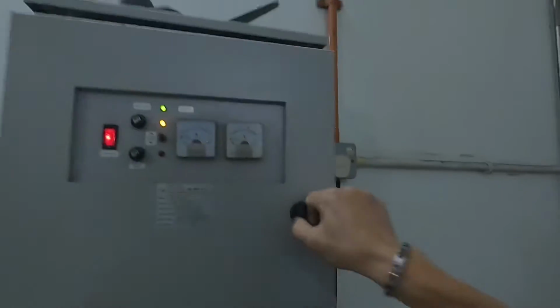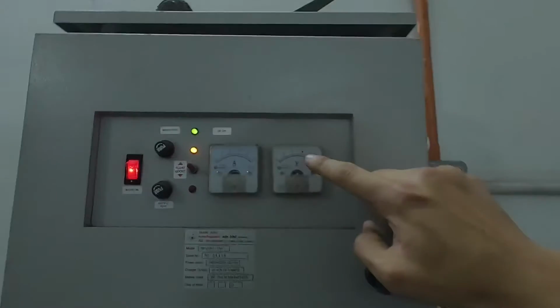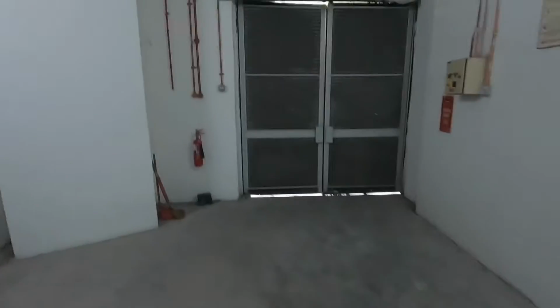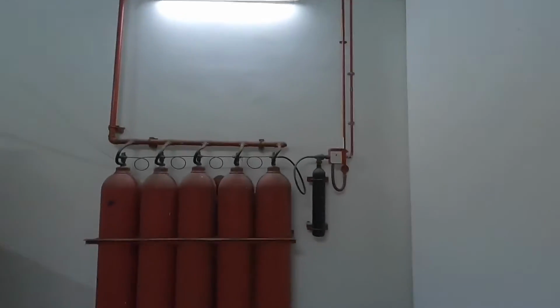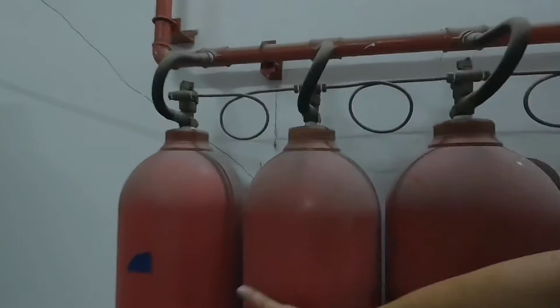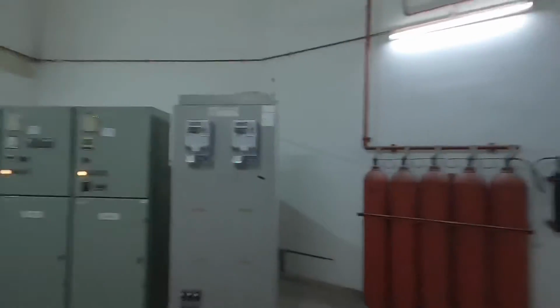Alright, then we have to make sure the safety parameters such as the tripping unit, battery is in good condition, voltage above 30 volt DC, charger function, rubber mat in place, fire extinguisher in place, CPR chart, electrical single line drawing, CO2 extinguishing system. The room is free from moisture and dry. Okay, then we'll proceed to another room then.